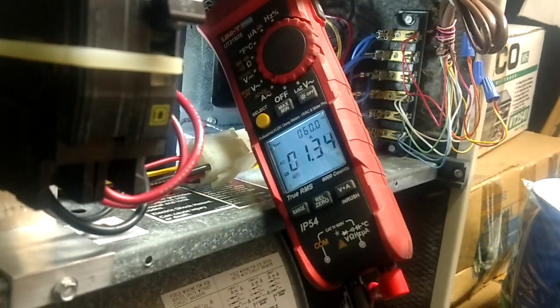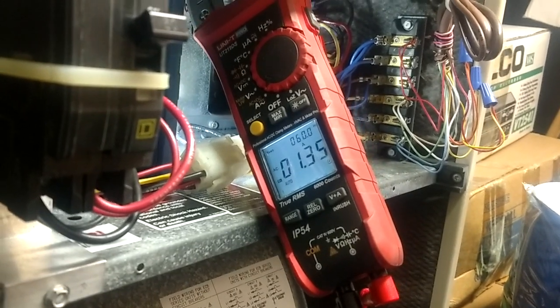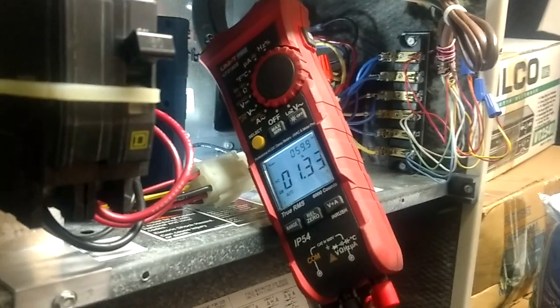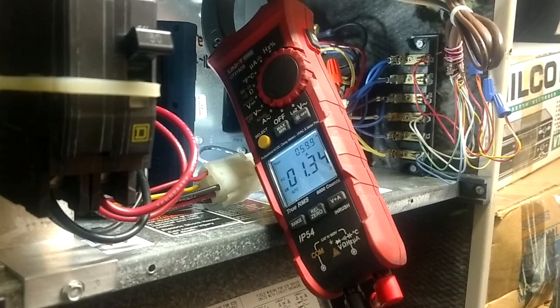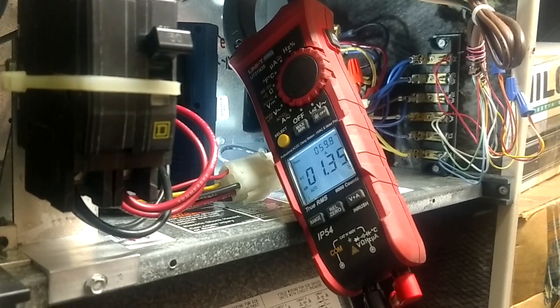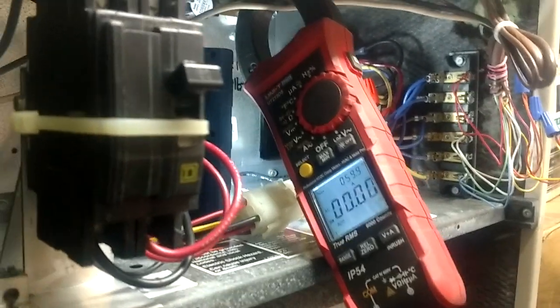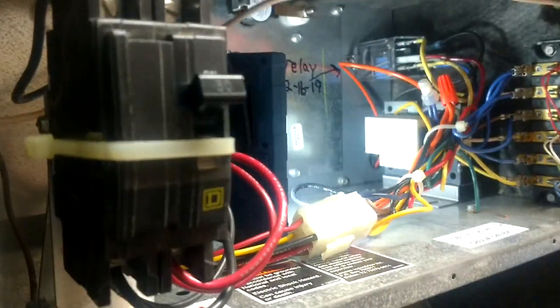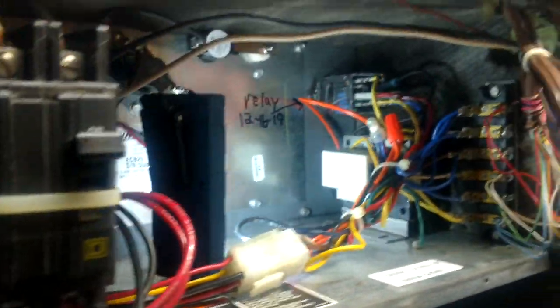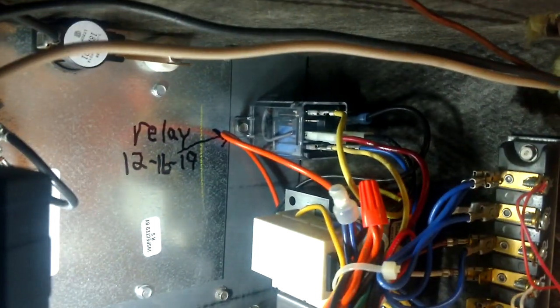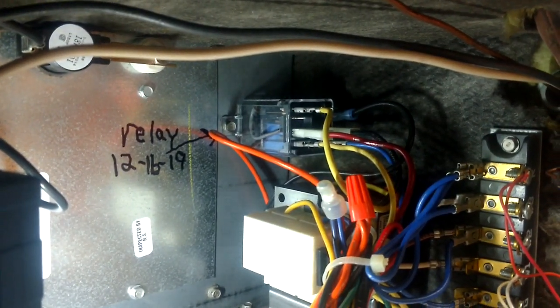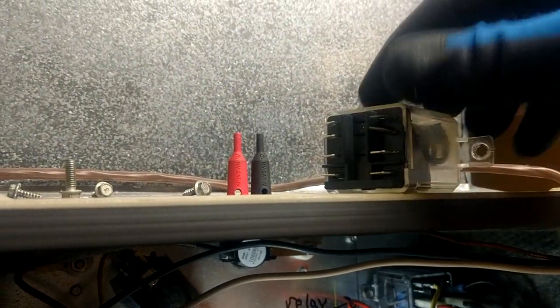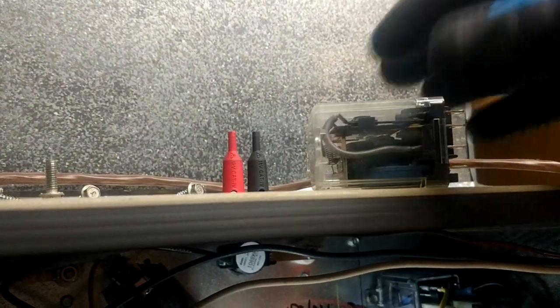So you see our heater is off. The sequencer is timing out the blower. We've got a few more seconds and it should turn off. There we go. All right, so we're good to go on that blower relay. I just thought I would go ahead and show you the finished product. We definitely had a problem with that one up there. She was bad.